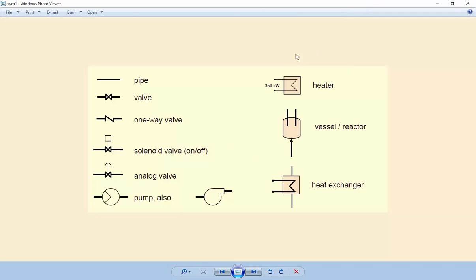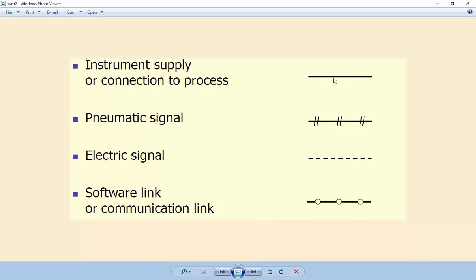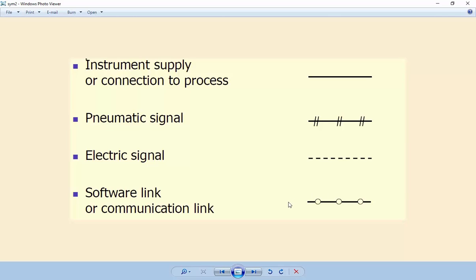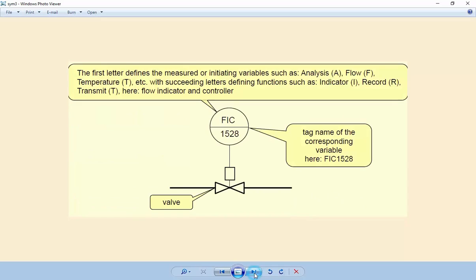These are basic symbols used in a P&ID diagram. You can download them from Google. This shows pipe, valve, one-way valve, solenoid valve, analog valve, heat exchanger, vessel, and heater. This line shows instrument supply or connection to process, this line shows pneumatic signal, this dash line shows electric signal, and this line is used for software link and communication link.